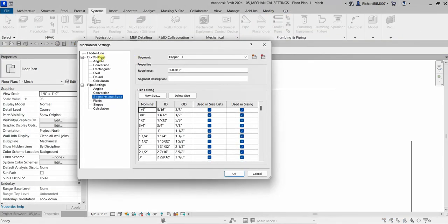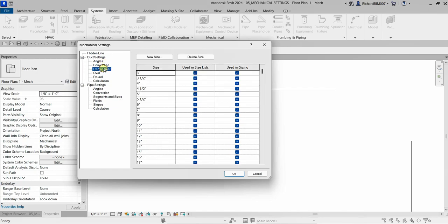From the mechanical settings for your duct, you have three shape options: rectangular, oval, and round duct — and there are settings for each in the mechanical settings dialog. The same rules apply: 'Used in Size List' controls sizes available in the duct tool, and 'Used in Sizing' controls which sizes the duct sizing tool will use.